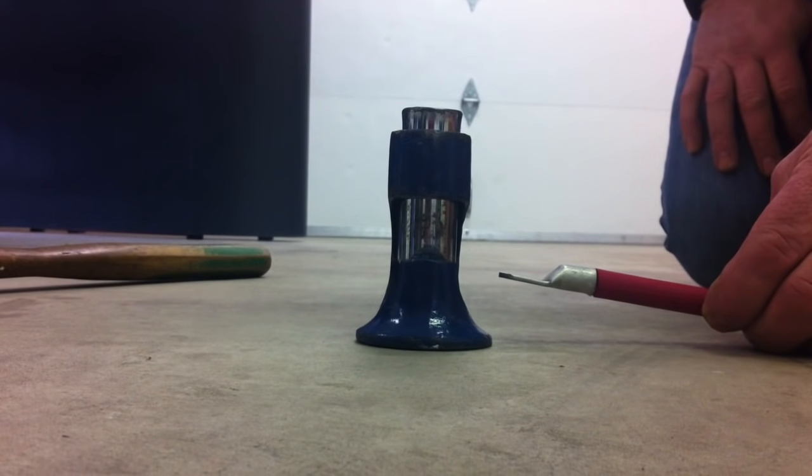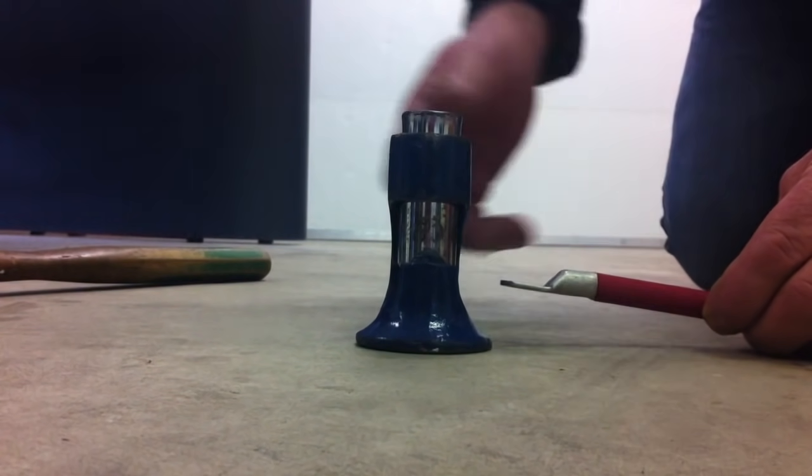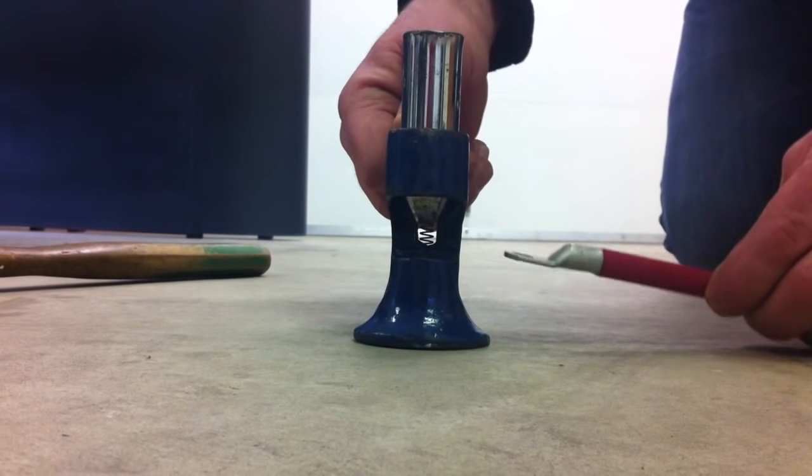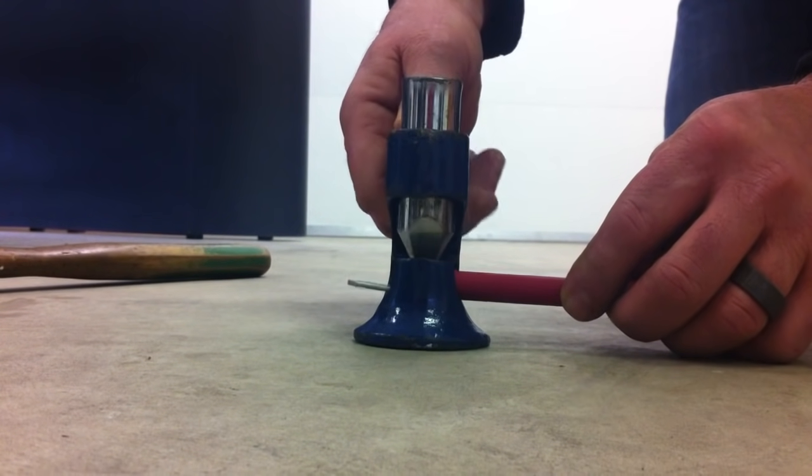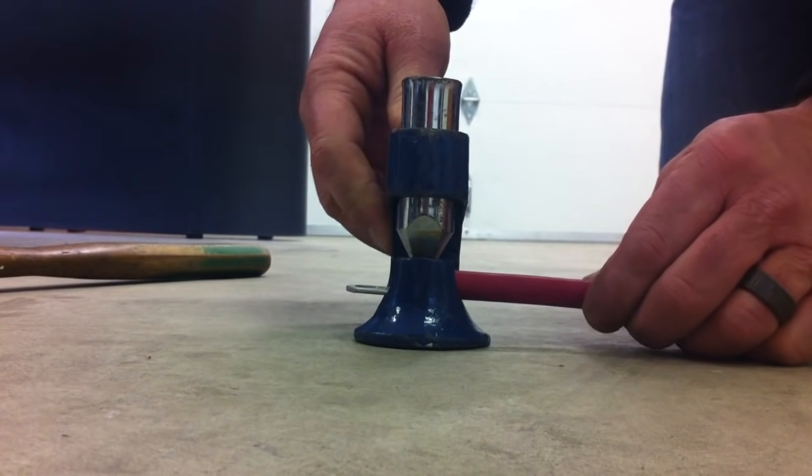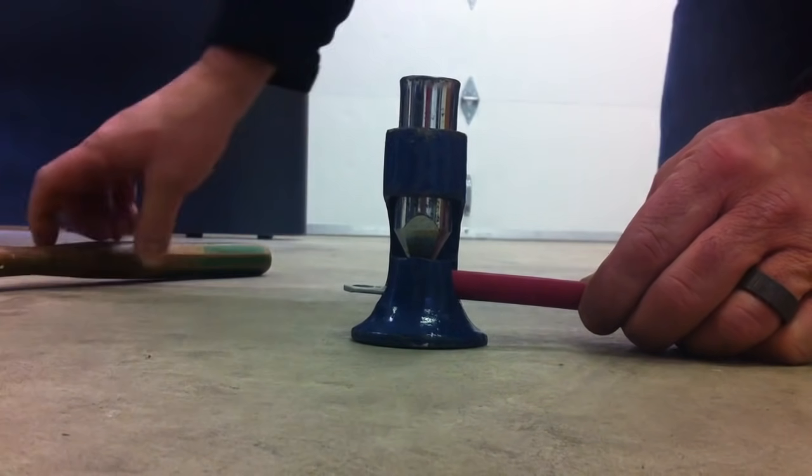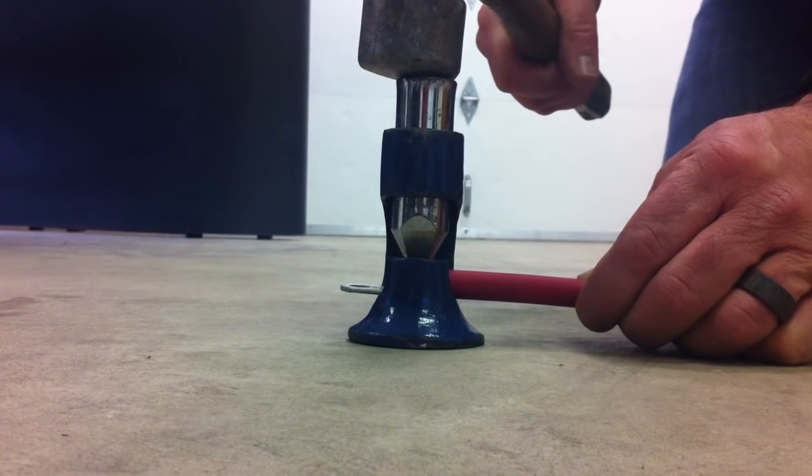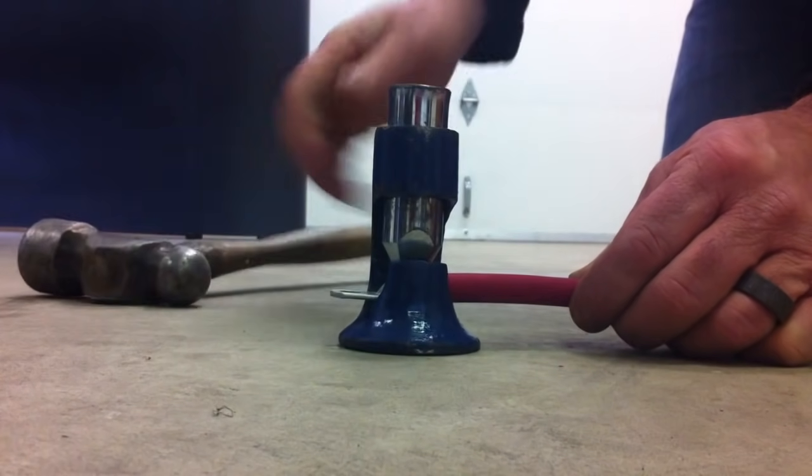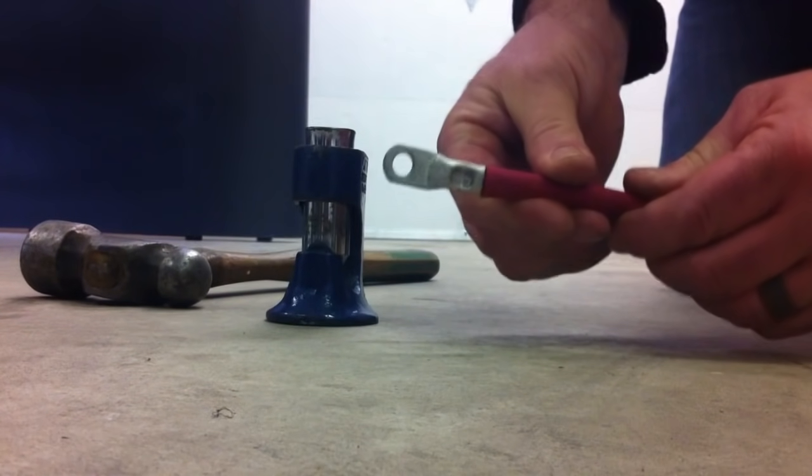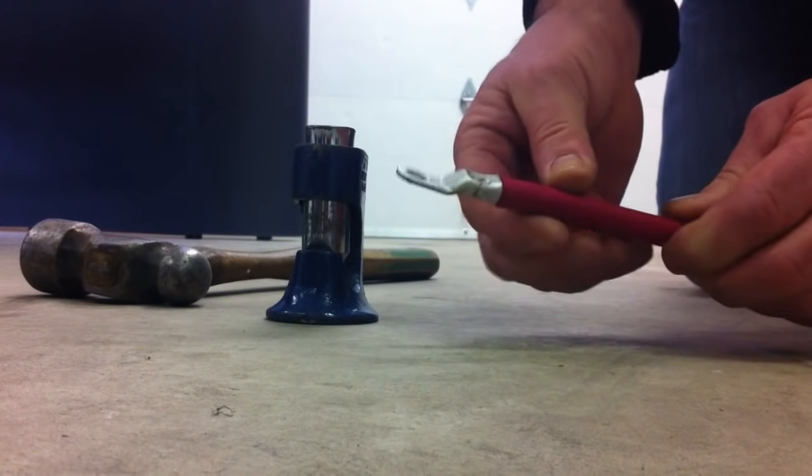Now that we've got our insulation stripped and our cable and our lug in place we're going to go into our crimper. We're going to place the lug into the crimper, make sure that the cable is butted in tight. We'll use our hammer and we're just going to give it one blow. And as you can see we get a nice firm crimp.